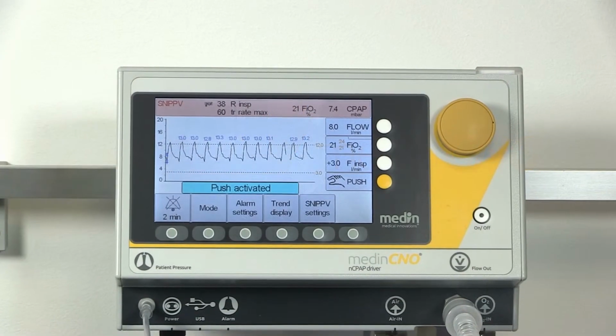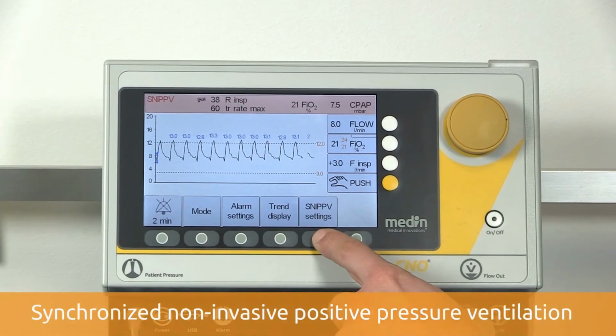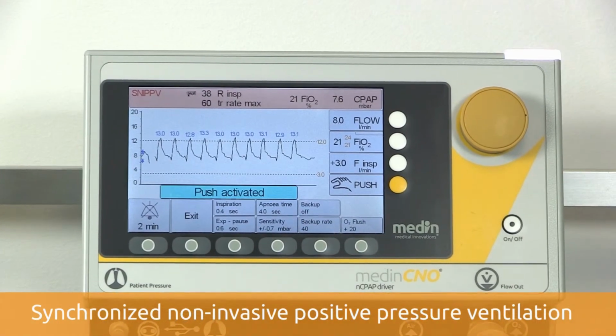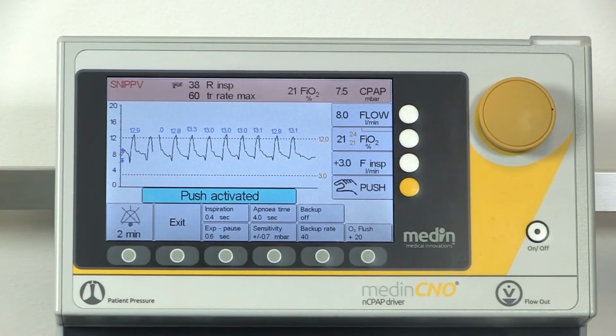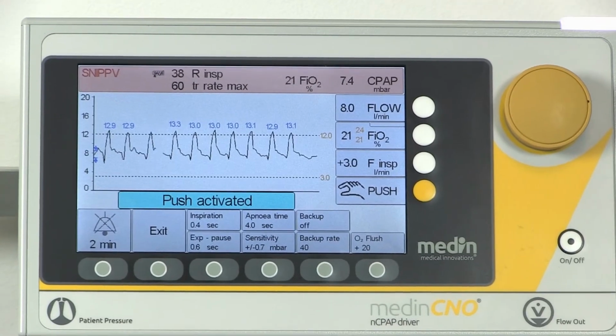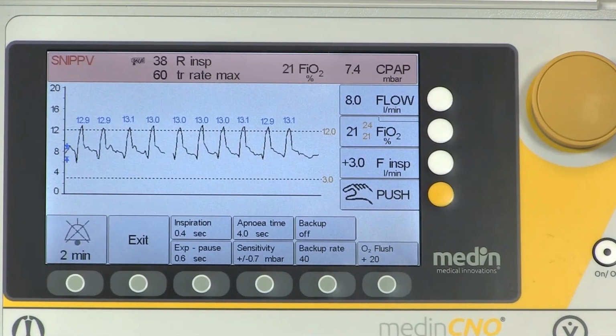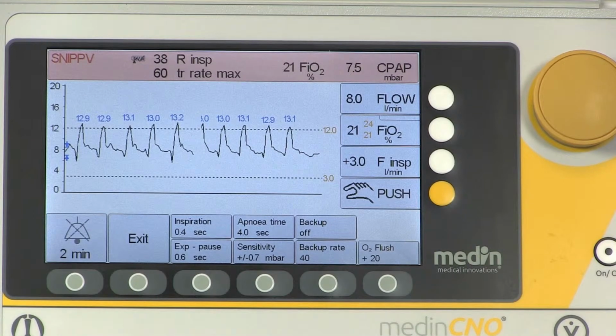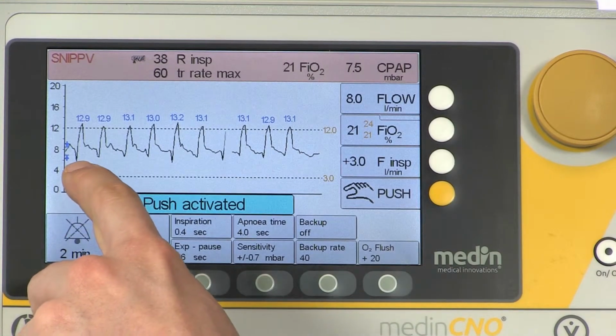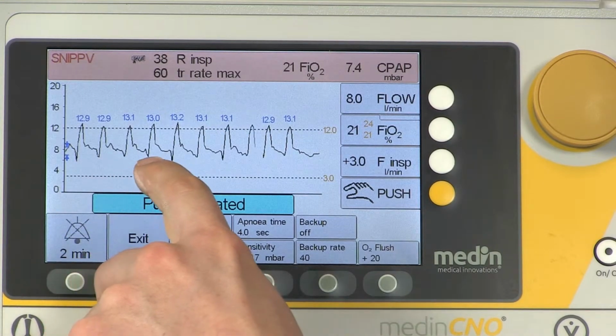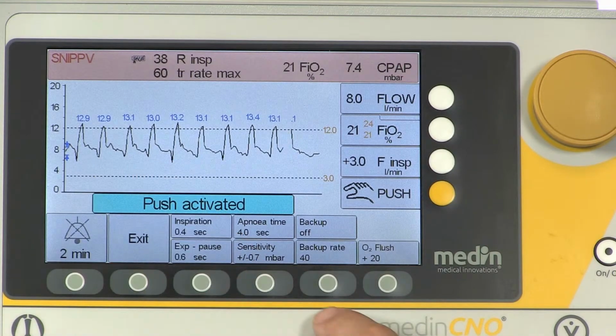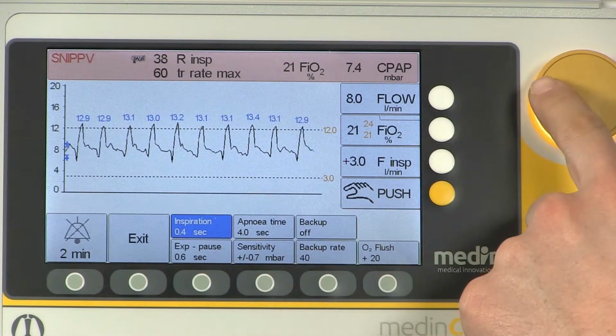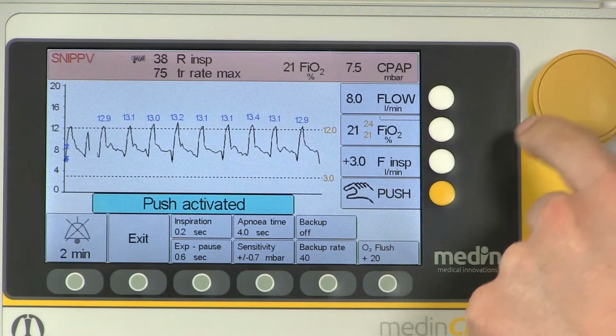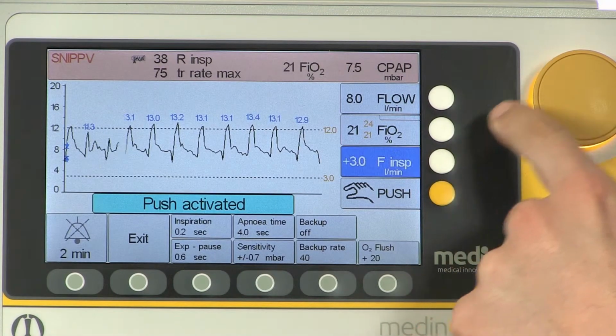The medinCNO offers an SNIPPV mode. During synchronized noninvasive positive pressure ventilation, the innovative pressure trigger detects the beginning of the baby's inspiration and supports it with an adjustable inspiratory time and a synchronized second higher pressure level.